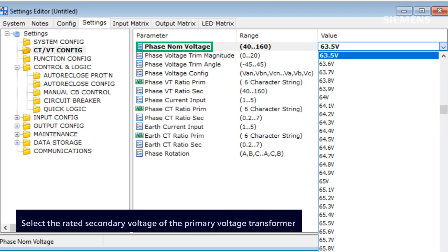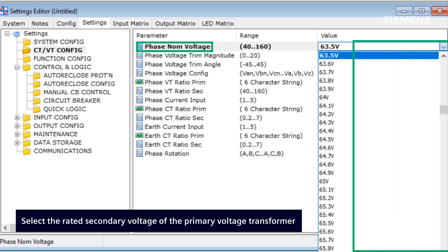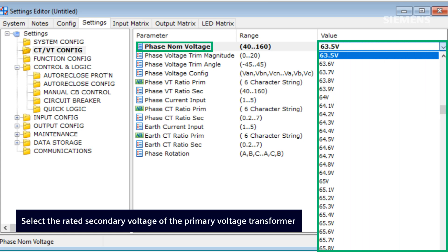The phase nominal voltage setting enables users to specify the rated secondary voltage of the primary voltage transformer. For instance, if the primary voltage transformer has a ratio of 132kV to 110V, you should select the phase nominal voltage as 63.5V.